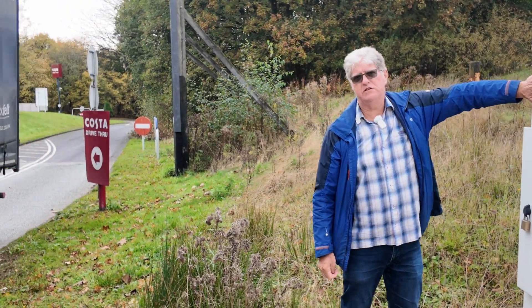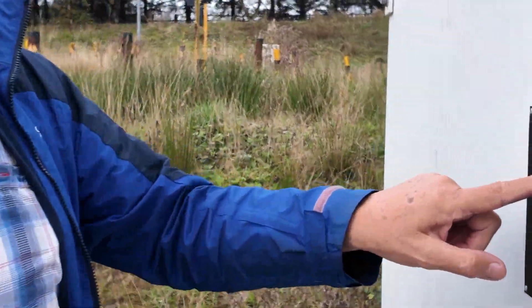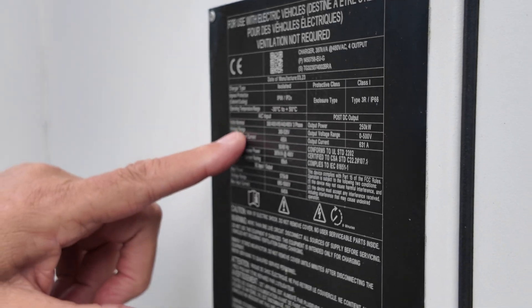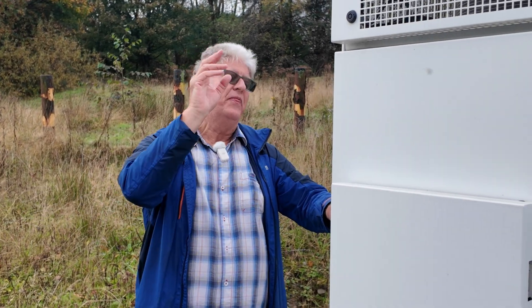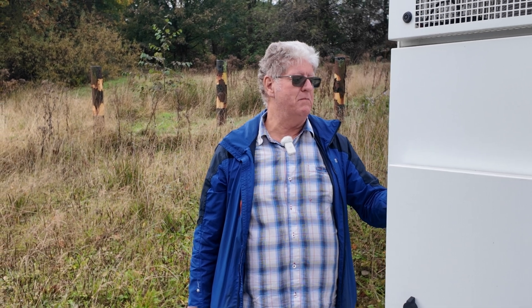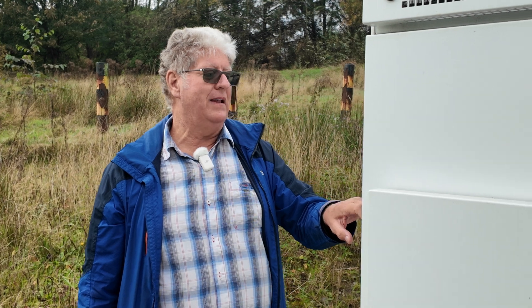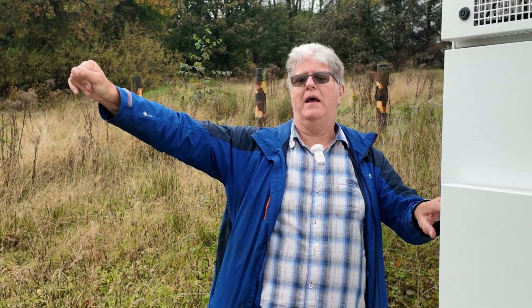These are the cabinets — three of them, each quite capable of a thousand kilowatts. On this one there's a label on the end, as all of them are. It's rated IP66, which simply means these are totally weatherproof — they can stand anything. Voltage input nominal: 380, 400, 415, 440, 480, three phase. That's what I was saying about Tesla superchargers — they like to get the transformer to supply not 415 but 480. The voltage range is 360 to 528, so quite a wide spread. Maximum input power 575 kilowatts, maximum voltage range 800 to 1,000 volts. Output power 250 kilowatts, output range 0 to 500 volts. So those will never be able to charge an Ioniq 5, which is an 800-volt architecture — these are all rated at 400 volts.